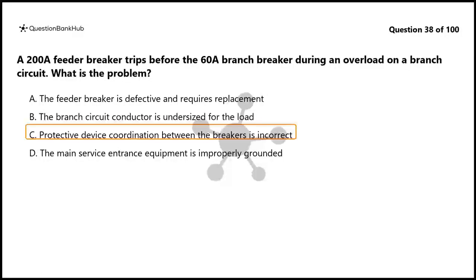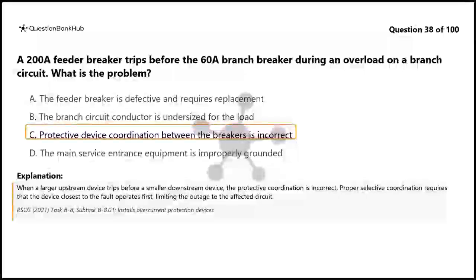The correct answer is C. Protective device coordination between the breakers is incorrect. When a larger upstream device trips before a smaller downstream device, the protective coordination is incorrect. Proper selective coordination requires that the device closest to the fault operates first, limiting the outage to the affected circuit.